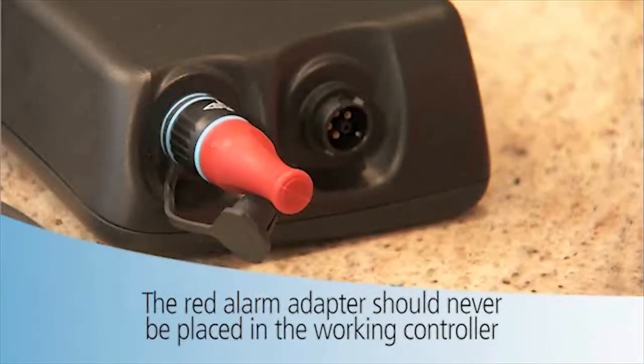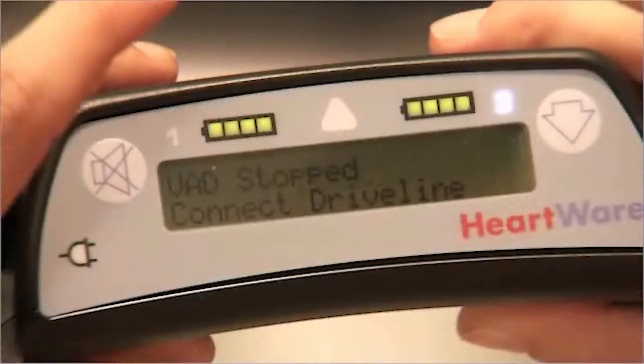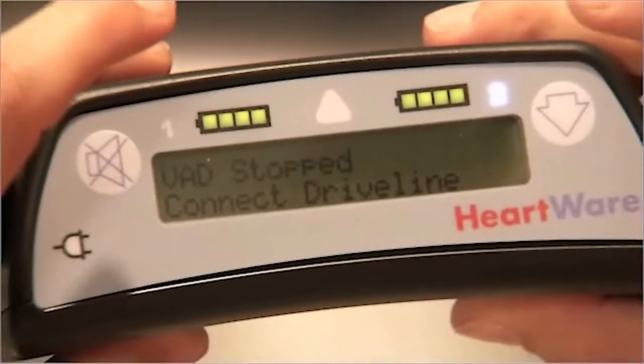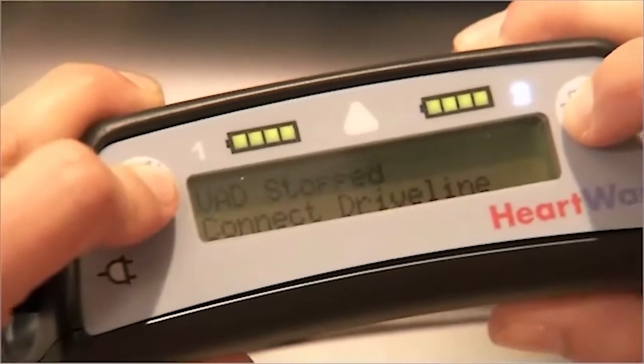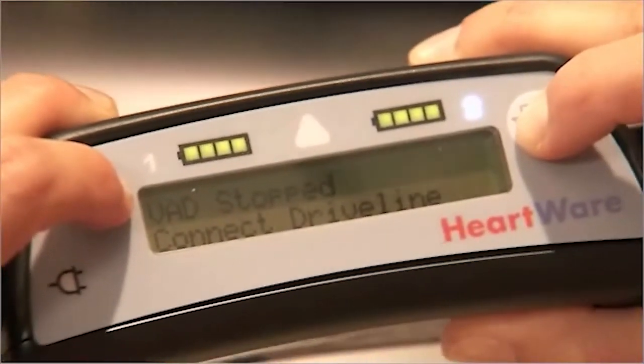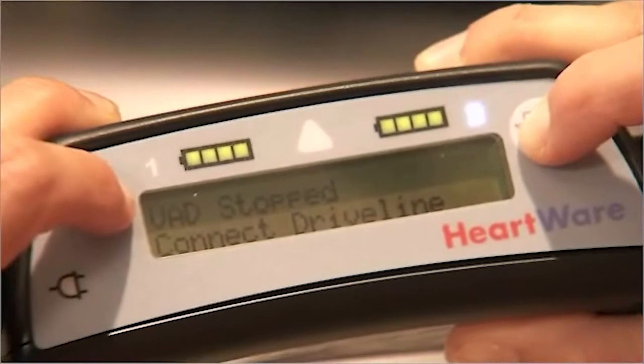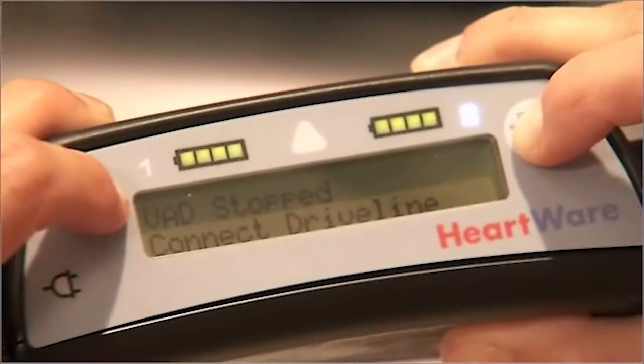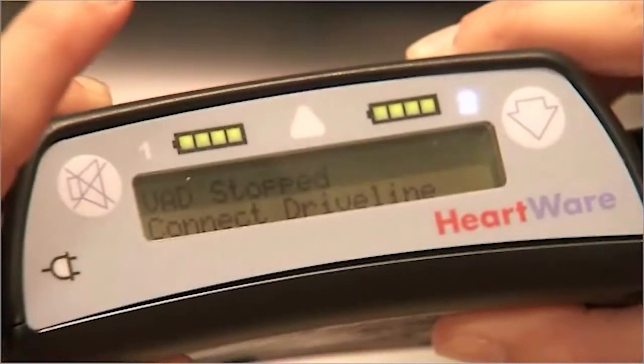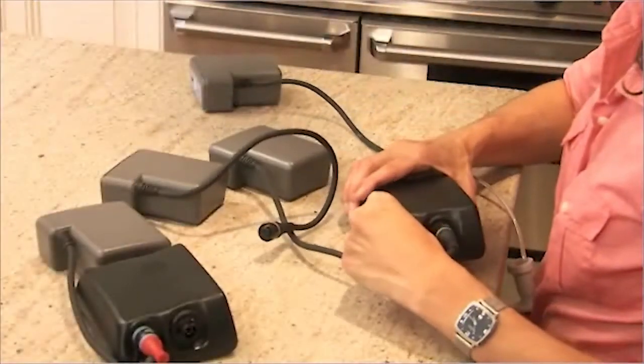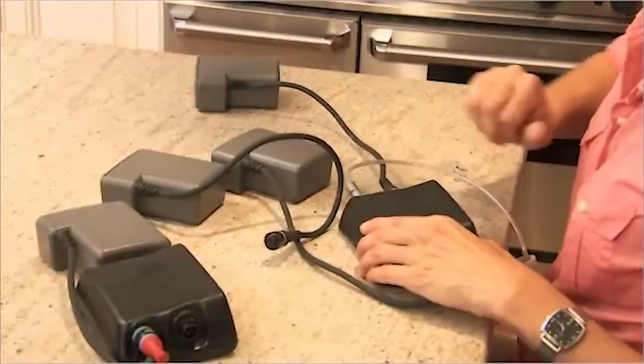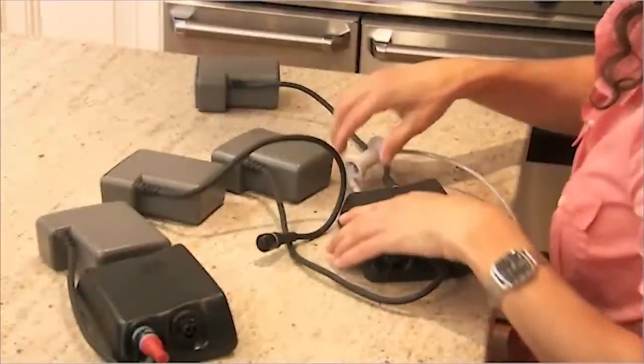If a red alarm adapter is not available, you can silence the no power alarm on the original controller by pressing and holding the alarm mute and scroll buttons at the same time until a beep is heard, or for at least 5 seconds. Release both buttons, then disconnect the power. The original controller will be turned off and all alarms silenced. On the new controller, slide the white driveline cover over the silver connector.